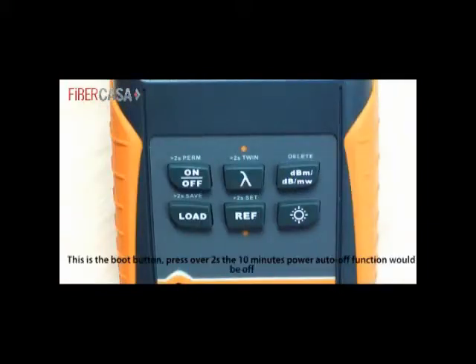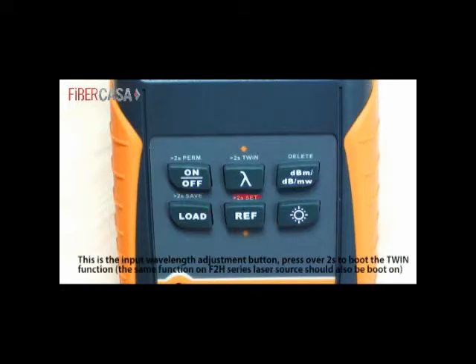Button function. This is the boot button. Press over 2 seconds, the 10 minute power auto-off function would be off. This is the input wavelength adjustment button. Press over 2 seconds to boot the twin function. The same function on F2H series laser source should also be booted on.